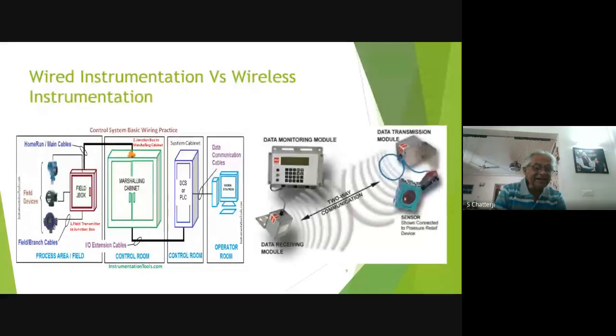From there it goes to the marshalling cabinet for control purposes. From the marshalling cabinet, it goes to the DCS or PLC, which is the part of the controller these days. As you all know, PLC and DCS are the main controllers in industries. So it will again have a lot of wires, thick wires and cables used here, and the data or signal will be taken from these wires to the DCS or PLC. The PLC will further give it to the workstation where it is to be processed.